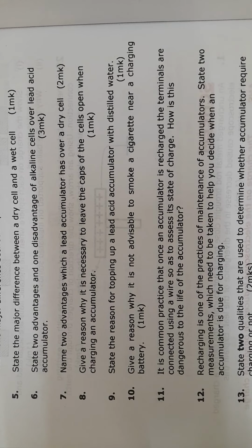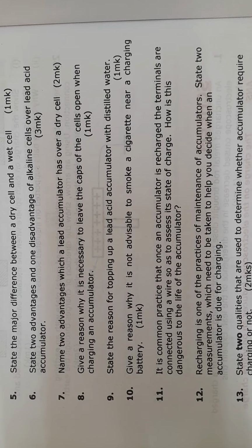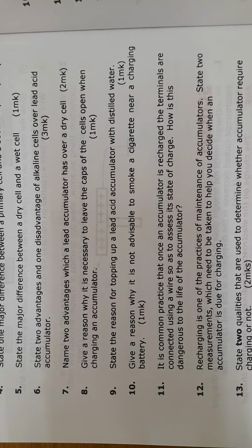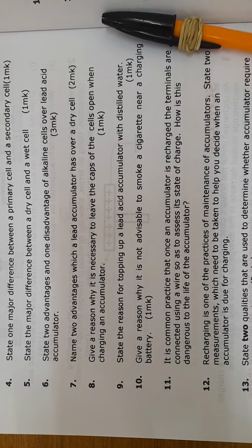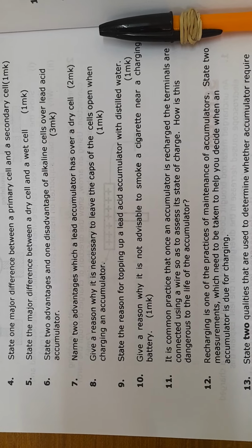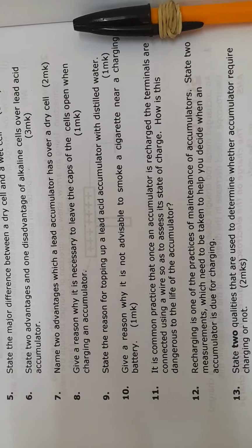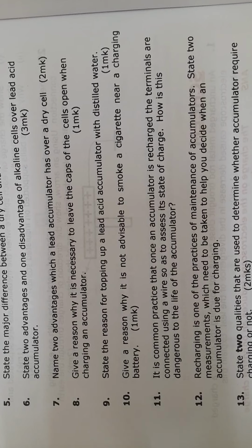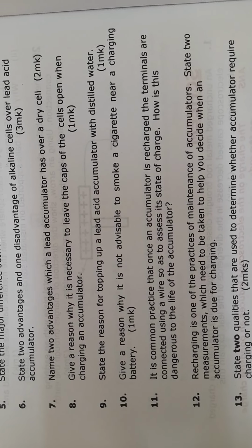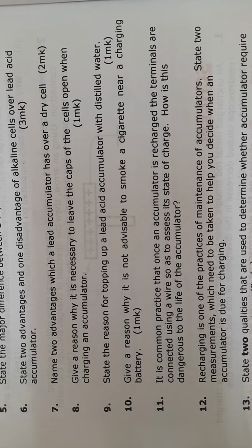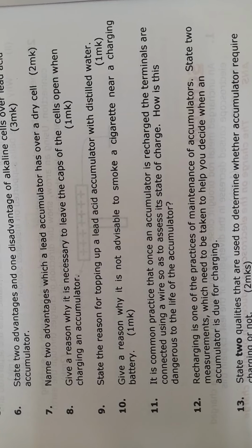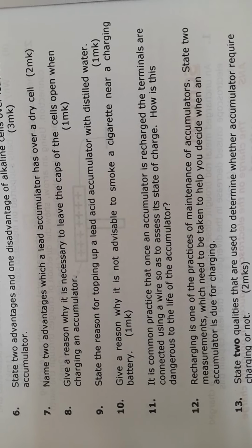You can see the next question there. It is saying recharging is one of the practices of maintenance of accumulators. State two measurements that need to be taken when an accumulator is due for charging. Sometimes you want to charge an accumulator, but you don't know whether it is time to charge it or not. The main point here is the EMF and the relative density. Those are the two measurements that need to be taken.